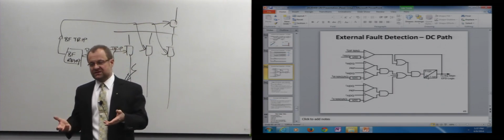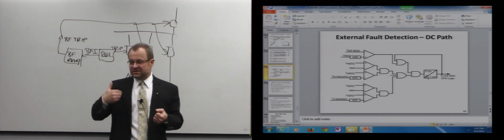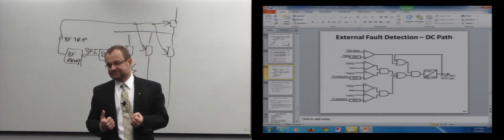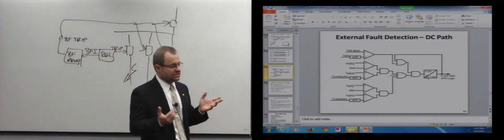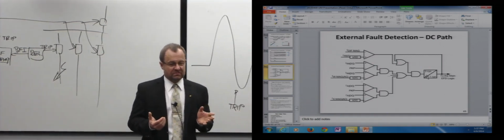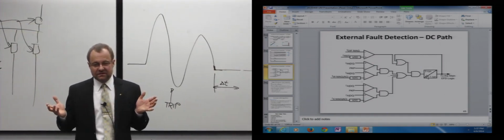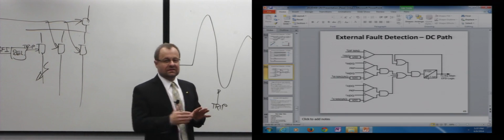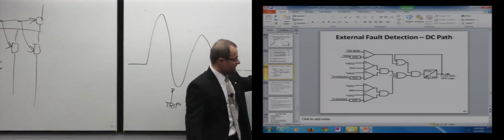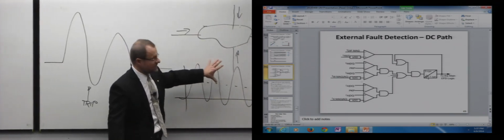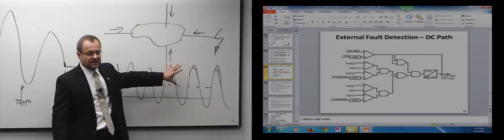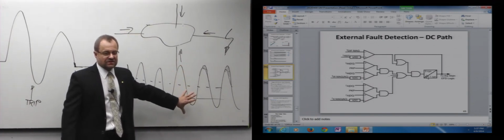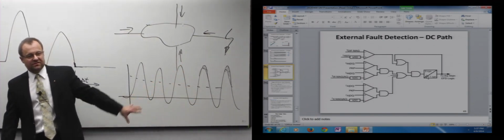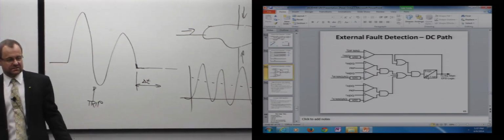And one of the things that you do is you energize a transformer from a generator. And then people realize that generator relays are tripping, misoperating left and right. And why is that? Because the transformer inrush current has a long-lasting inrush, DC. That DC causes saturation, and generator differential function misoperates.